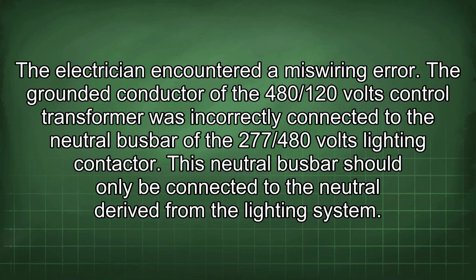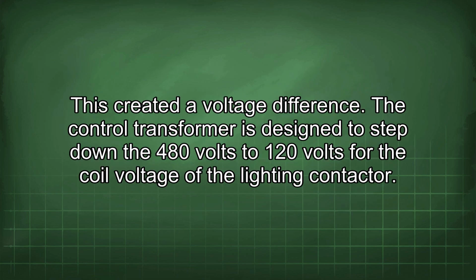The electrician encountered a miswiring error. The grounded conductor of the 480/120 volts control transformer was incorrectly connected to the neutral busbar of the 277/480 volts lighting contactor. This neutral busbar should only be connected to the neutral derived from the lighting system. This created a voltage difference.